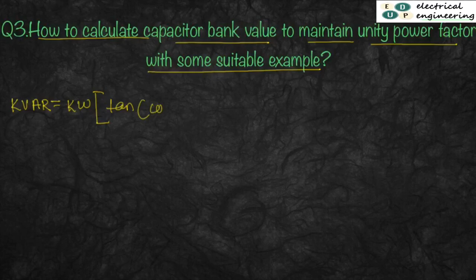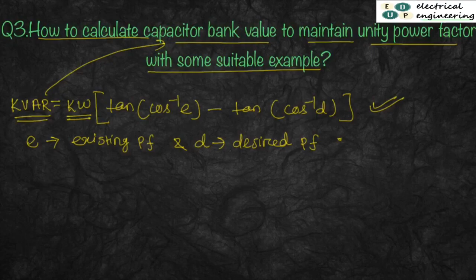Okay, you just need to remember this formula, where E is your existing power factor and D is your desired power factor. And here kilowatt is your system loading, and kVAR is the rating of the capacitor bank. So you just need to remember this formula, and you are supposed to apply it when you are going to use the capacitor bank to improve the system power factor.